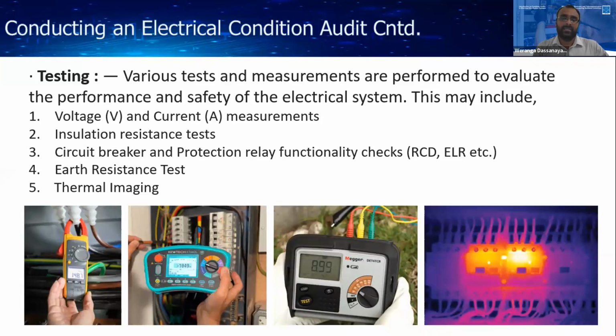For a single-phase system, our voltage is 230 volts. The maximum voltage drop at equipment level is 8%. If it is a light circuit, it should be 5%. More than that, we cannot say the system is in good condition, because the voltage is dropped and equipment can be damaged if you use that system.